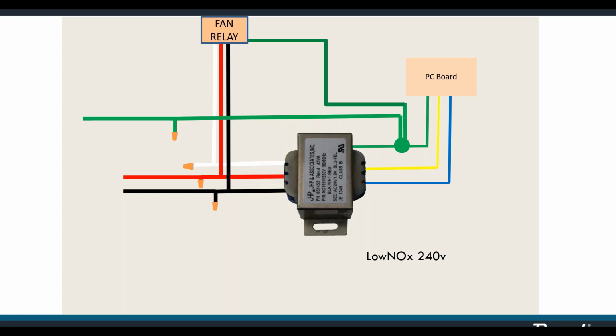The fan runs through a relay, which is wired with the transformer. Both the relay and the transformer have the same 3 wires in the same colors. Each colored pair is already twisted together at the factory. So you just treat those 2 wires as if they are one and wire accordingly. So there's no difference in wiring the Low NOx model. You just have an extra wire of the same color.